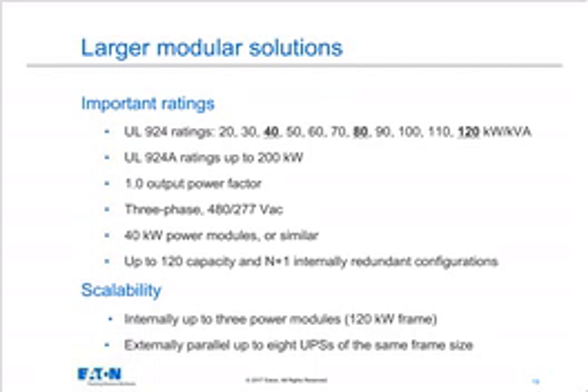Typical things that you'll see specified in this type of system: output power factor 1.0, so the kVA and the kilowatts are the same. Remember, your loads may be lighting ballast for fluorescent, and you want to think about what the power factor is and whether it's leading or lagging. Most modern UPSs can handle it either way.